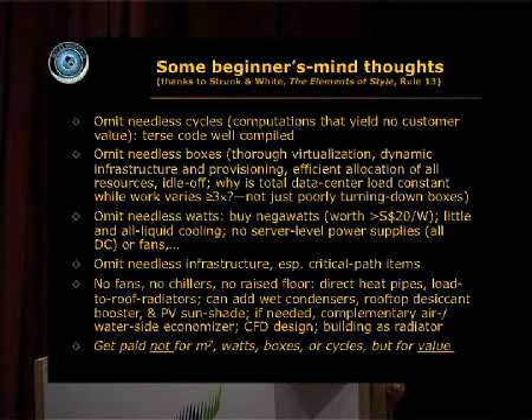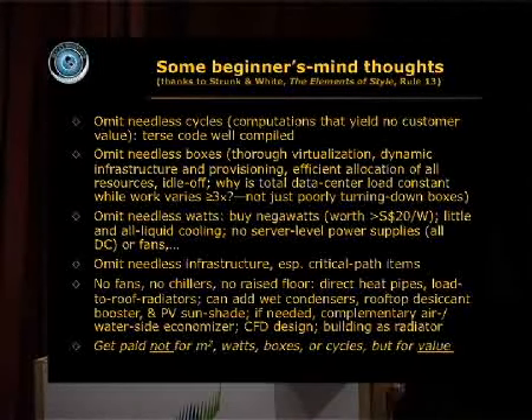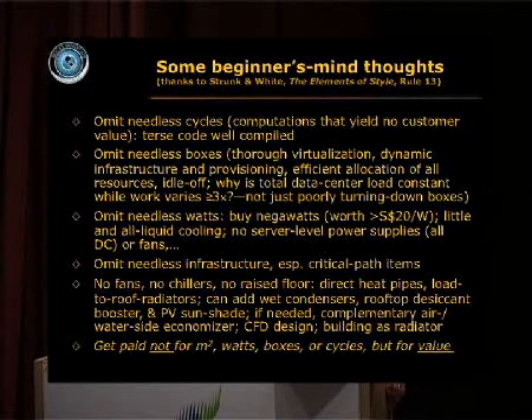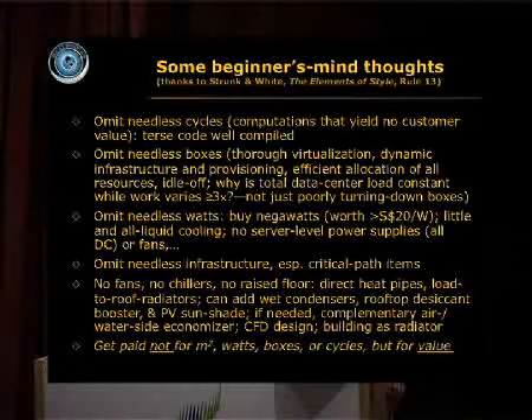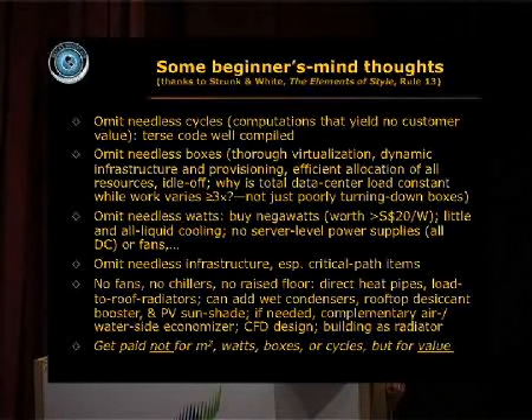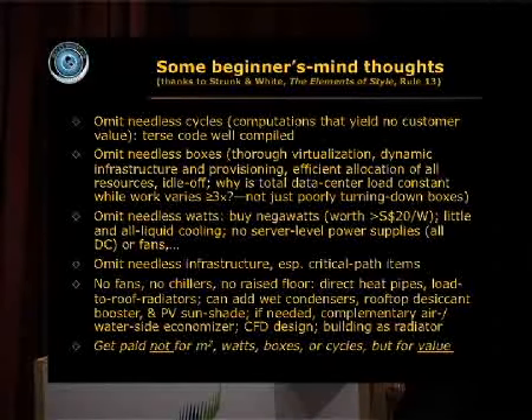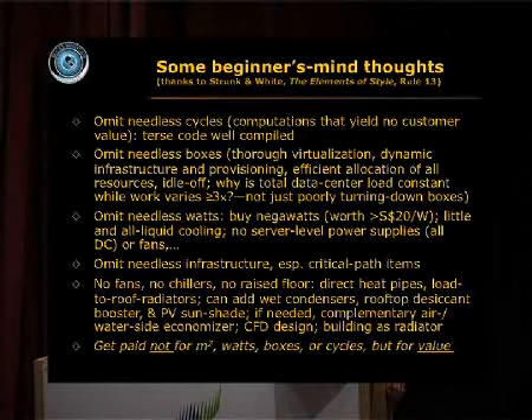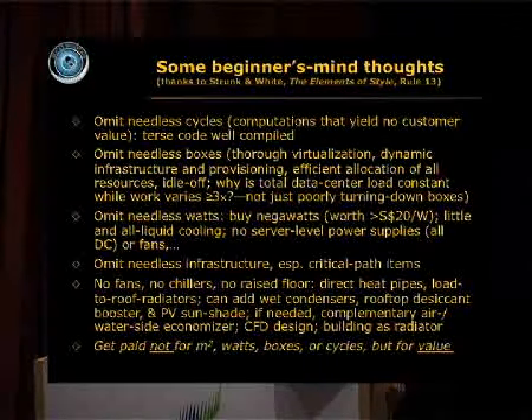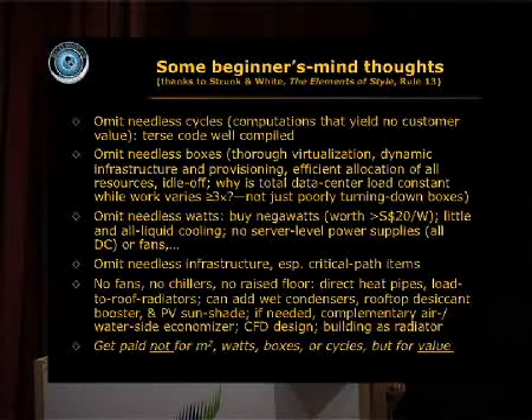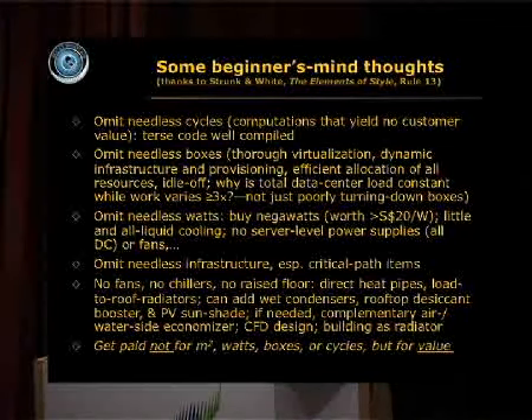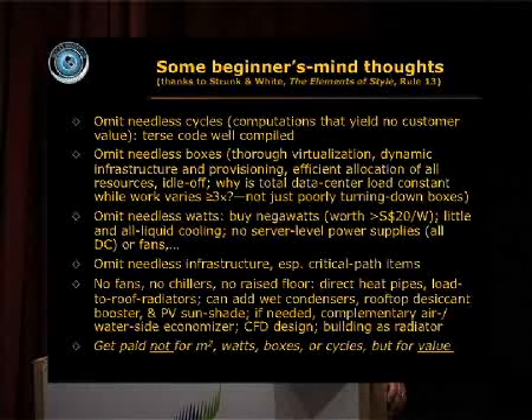And just think about it. If we have direct heat pipes from the backplane, they can run right up through the roof and radiate up there. No fans, no chillers, no raised floor. You can add, if you want, wet condensers if you're in a dryish climate. You could add a rooftop desiccant booster. You could add a sunshade over the radiators and make it photovoltaic for your most critical loads. And if you want to, you can use complementary air and water side economizers with computational fluid dynamics designed for passive cooling. Or maybe you can engineer the entire building to be a radiator. You're paying for structure. Maybe you can have an extra function of rejecting heat.